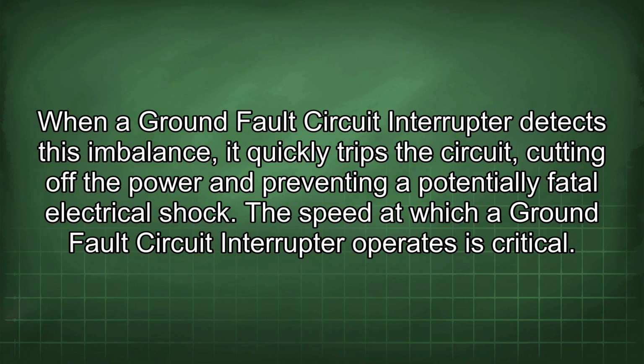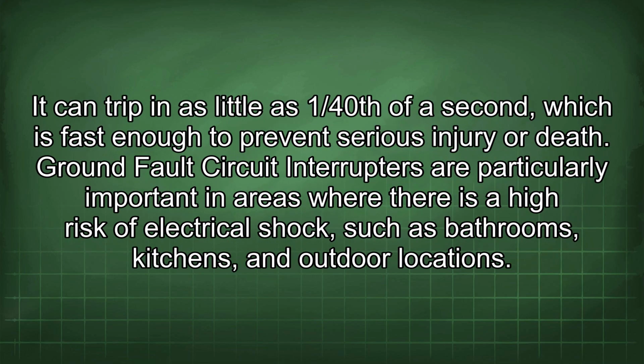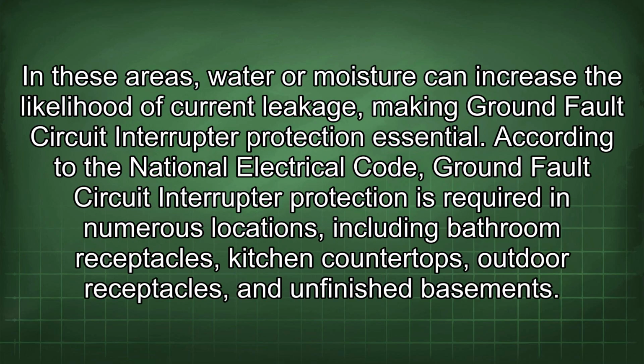The speed at which a ground fault circuit interrupter operates is critical. It can trip in as little as 1/40th of a second, which is fast enough to prevent serious injury or death. Ground fault circuit interrupters are particularly important in areas where there is a high risk of electrical shock, such as bathrooms, kitchens, and outdoor locations. In these areas, water or moisture can increase the likelihood of current leakage, making ground fault circuit interrupter protection essential.